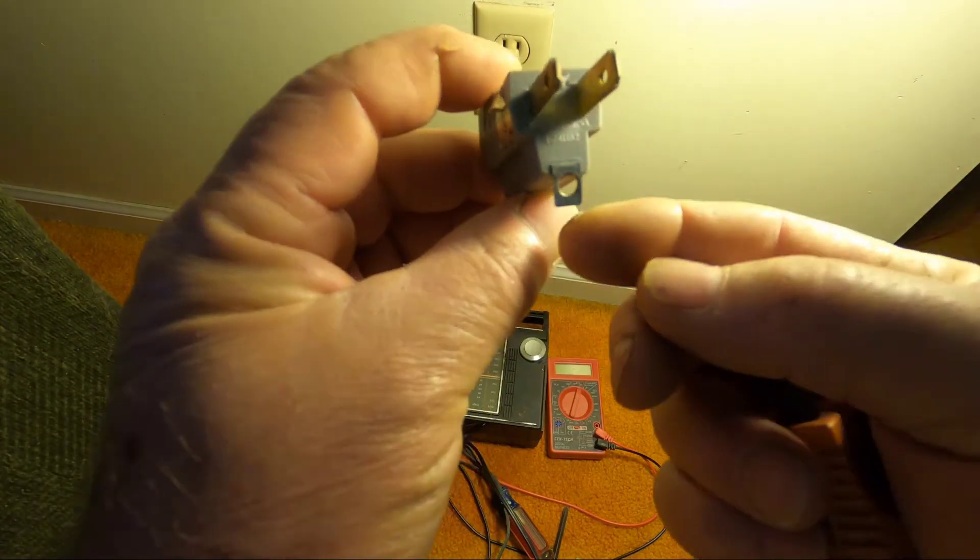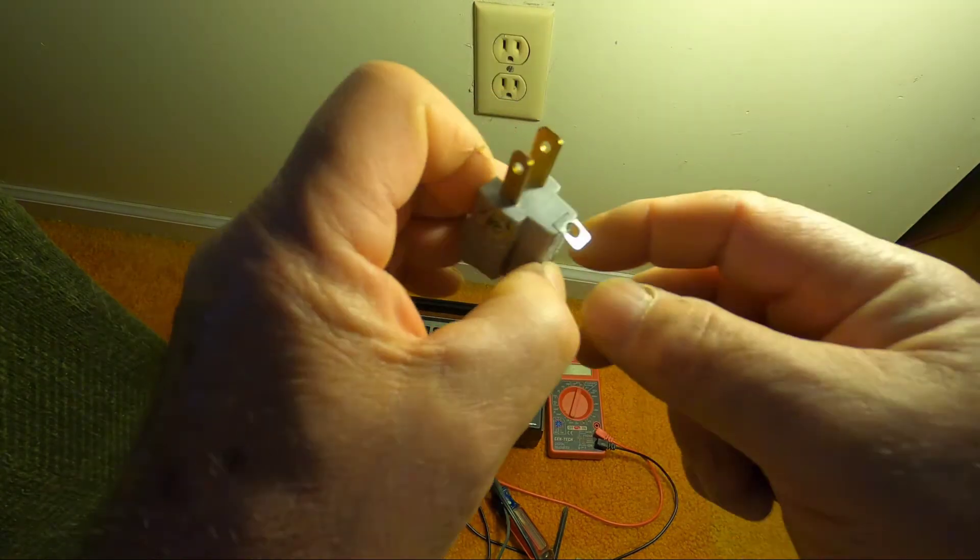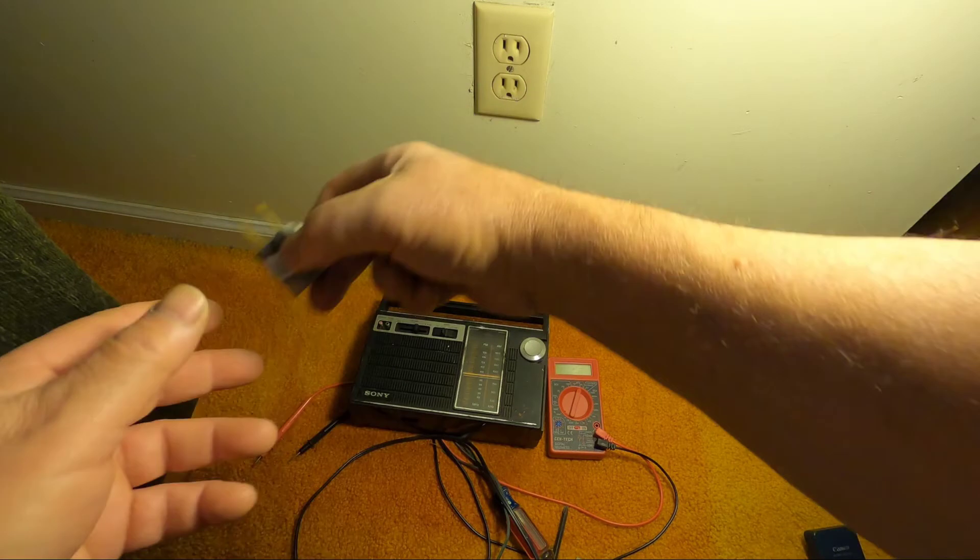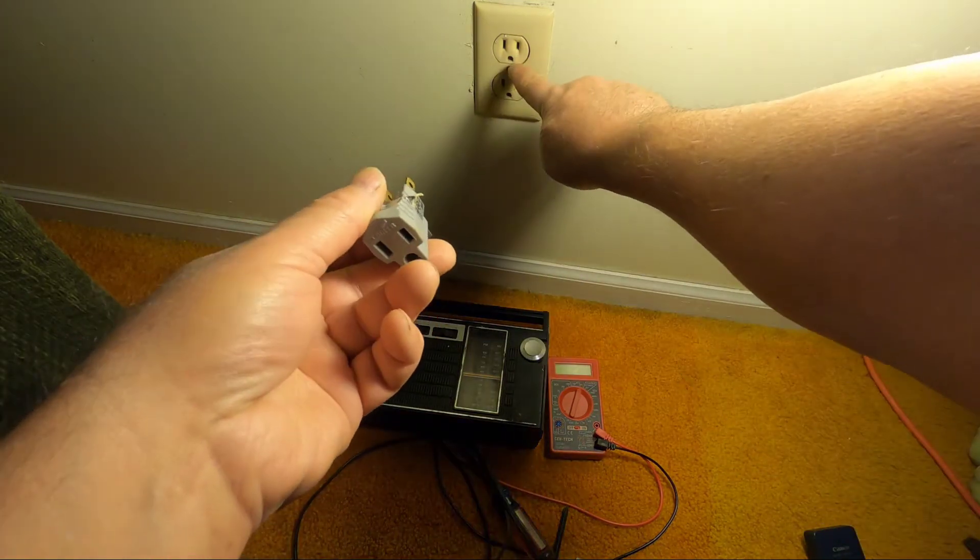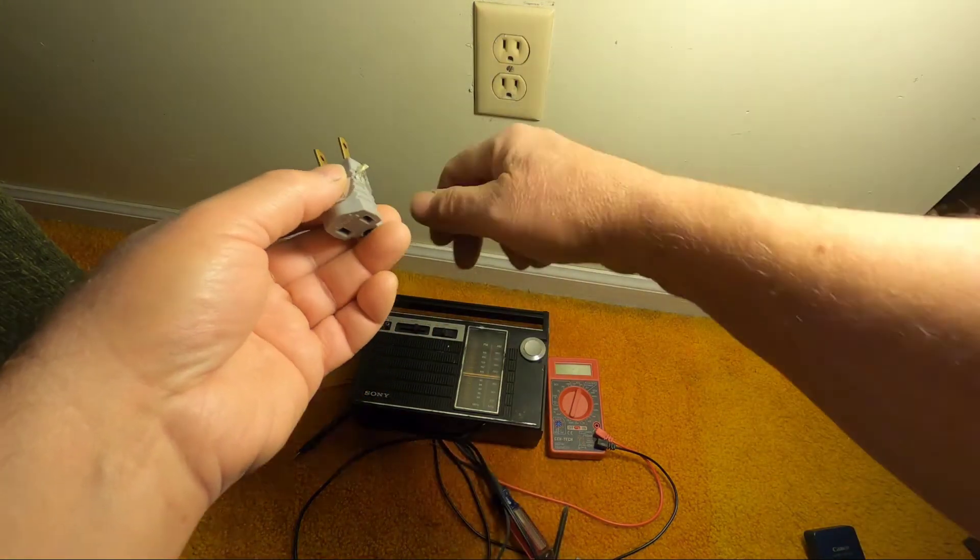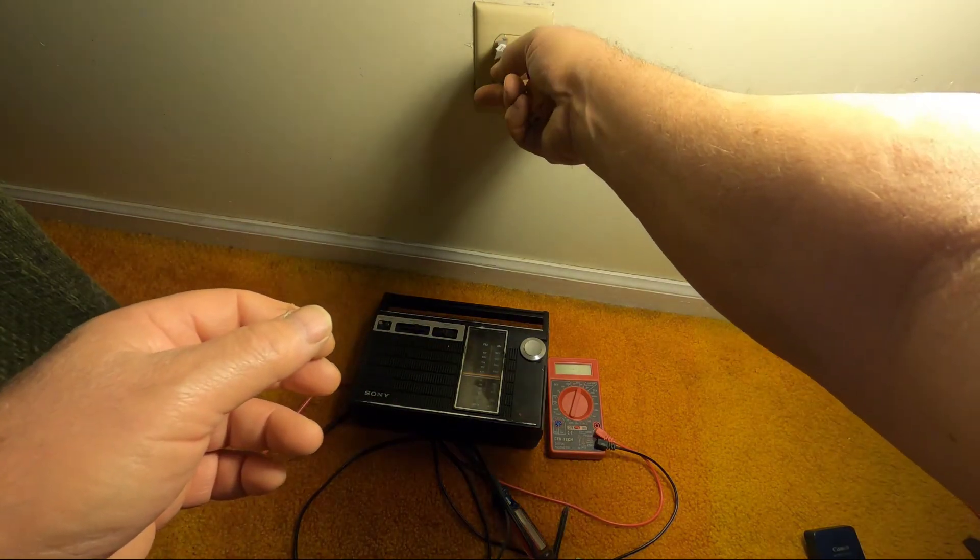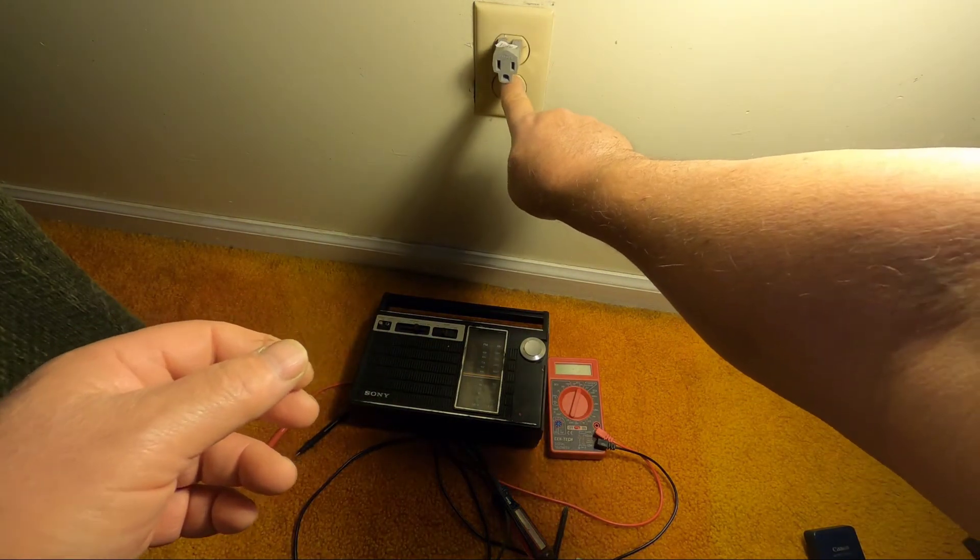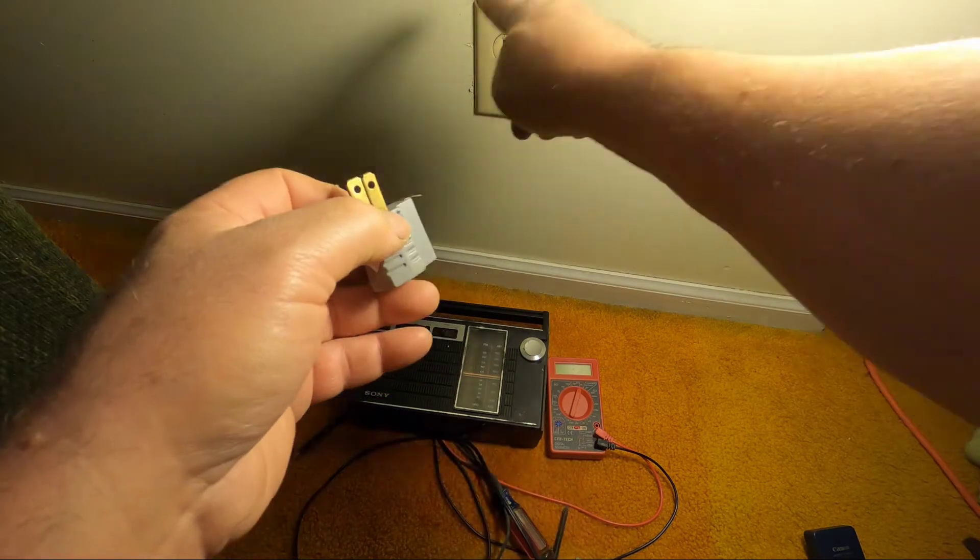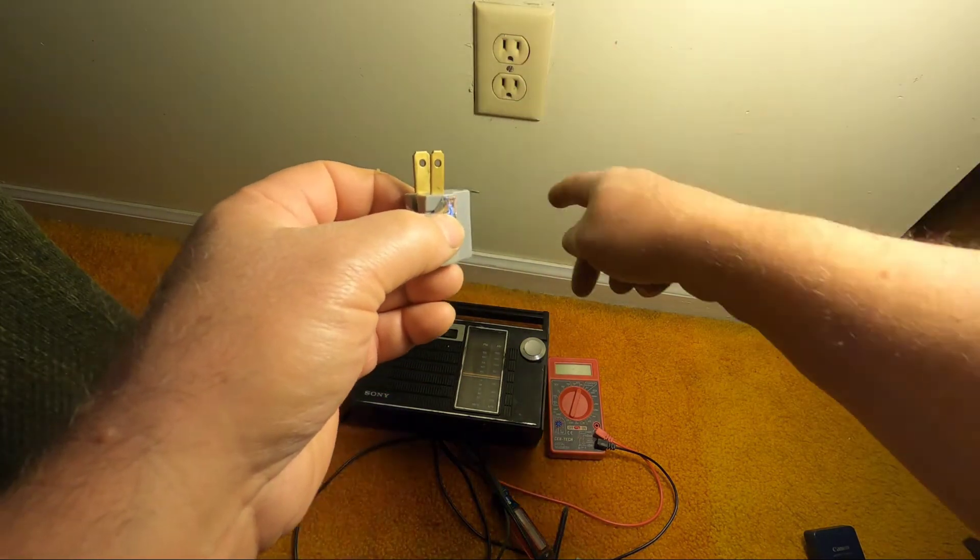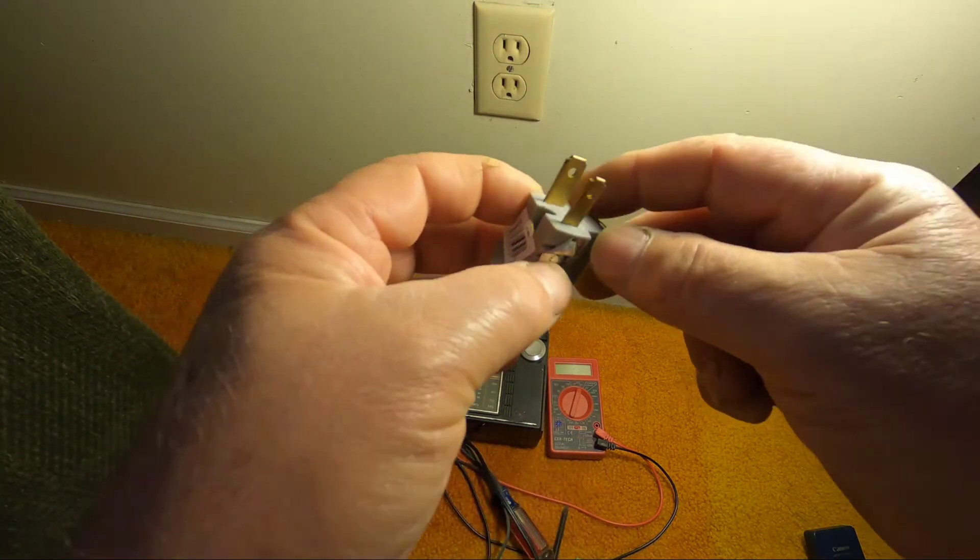For that one, you would get something like this. See this tab down here? When you plug this in, before you plug this in, you would take the screw that holds the plate out, plug it in, and put that screw in, and then you would have your ground, because that would be a metal box on the inside.